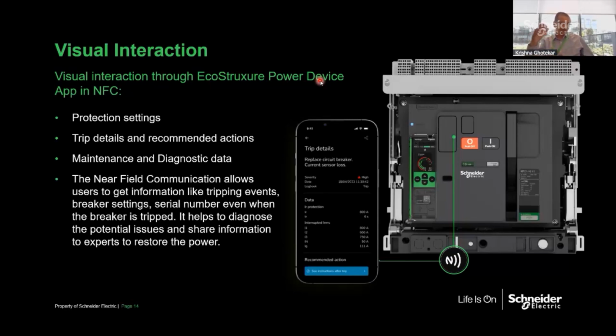But as of now, this feature is started with MTZ Active. In future, we will add other circuit breakers also, so you can test MTZ Active as an incomer, or MTZ Active as an outgoing, or MTZ Active as an incomer and NSX MCCB as an outgoing. So this is again an industry first, where the manufacturer is not only giving the discrimination tables or the test certificate, but you can live test the combinations as per the selections. And of course, if you have to do a secondary injection testing, then there is a paid license.